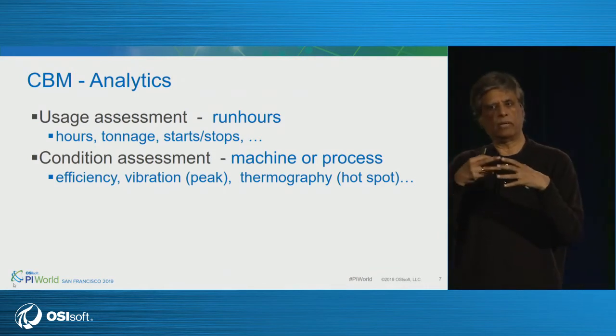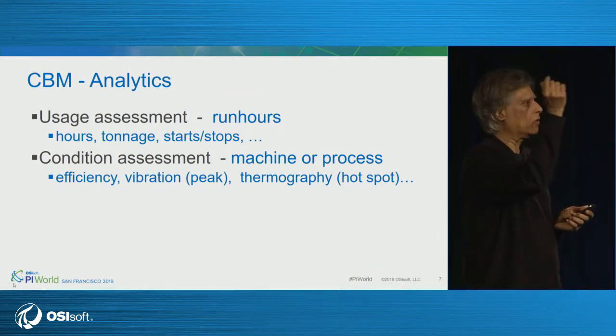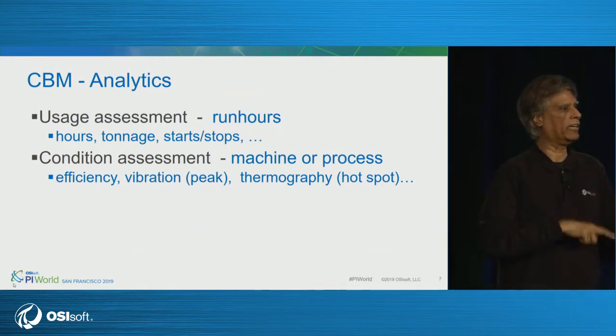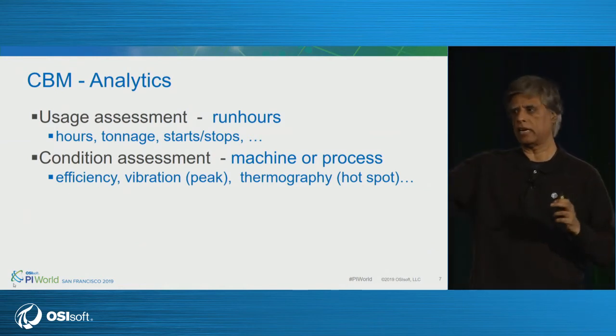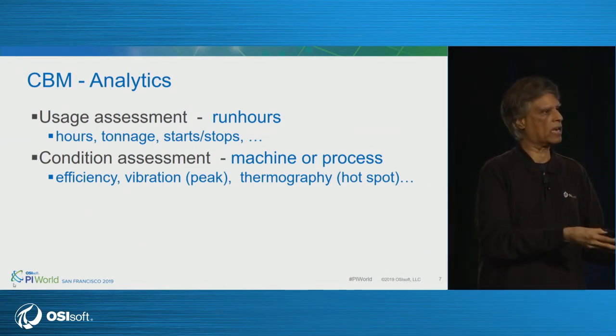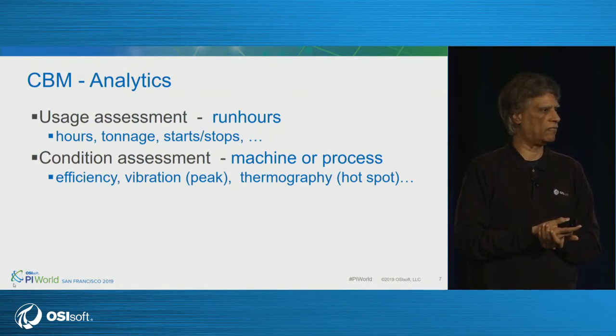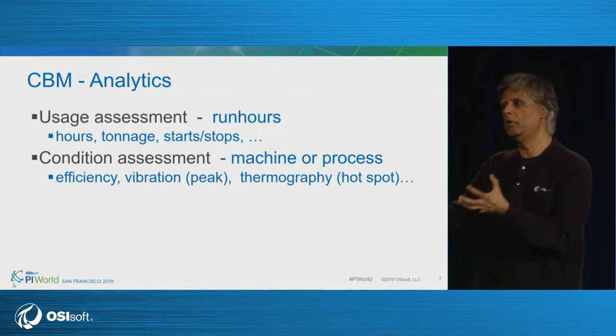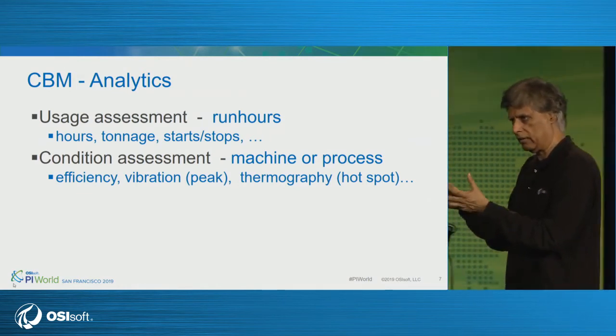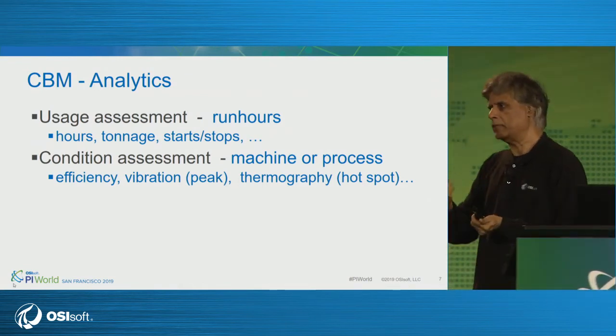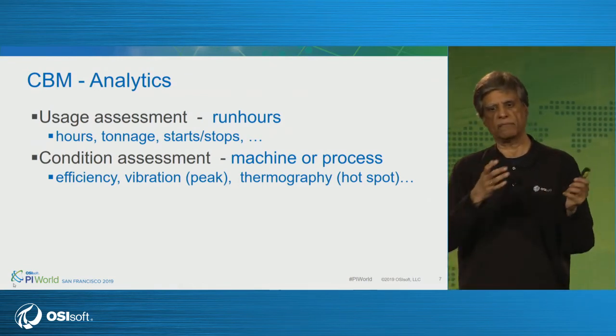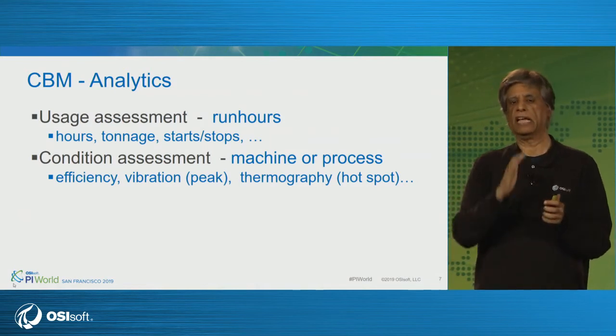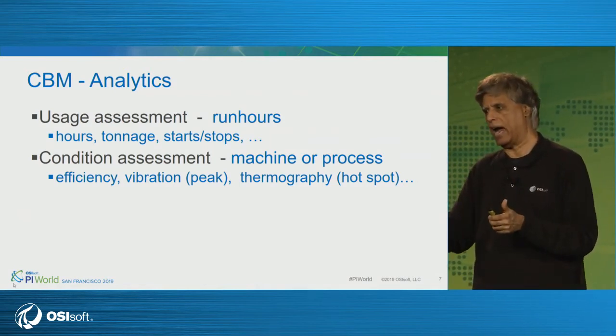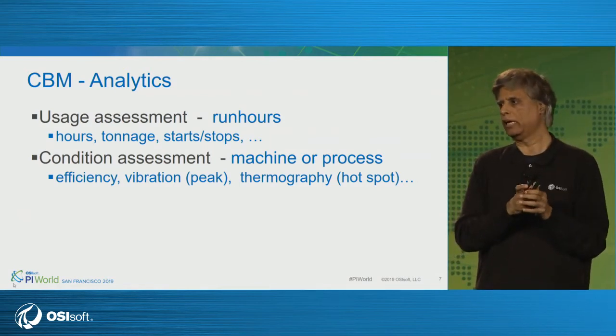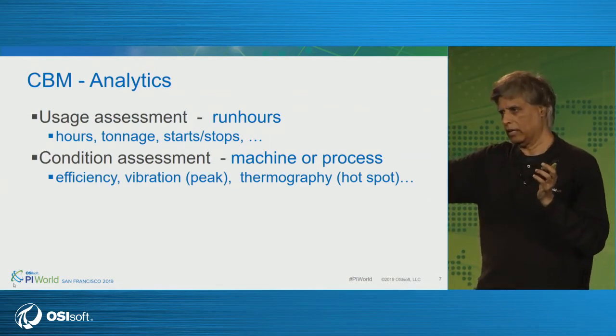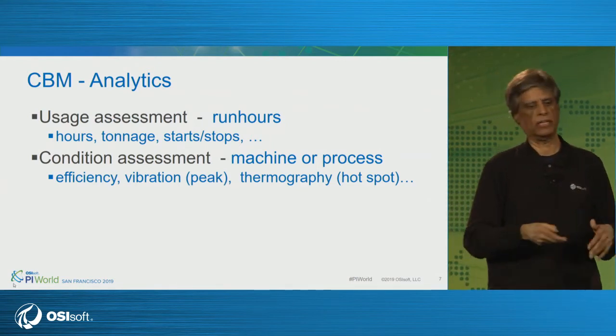For example, in a steam condenser, I can watch the steam flow and tell you the condenser is fouled if the steam isn't condensing properly. I'm not using the fouling factor itself, just the amount of steam not condensing, because that will progressively get worse — all the steam sent through the condenser will come out without condensing properly. So that's an indication, and there are different ways of doing condition assessment as part of your maintenance business process.